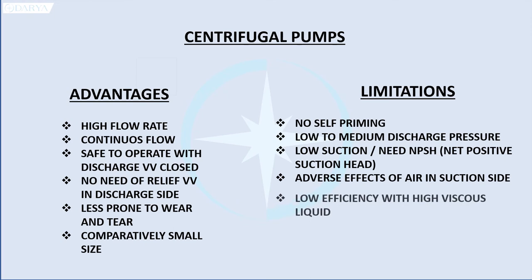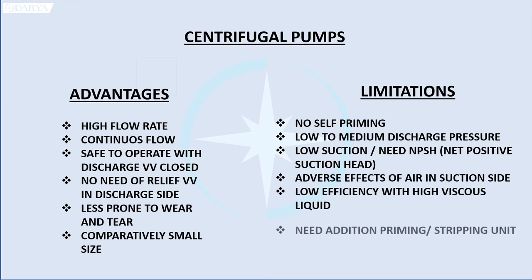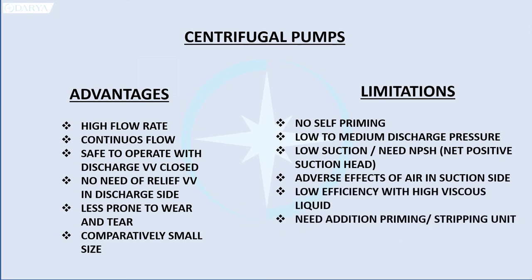They have low suction and need net positive suction head. There are adverse effects of air in suction side. They have low efficiency with high viscous liquid and need additional priming or stripping unit.